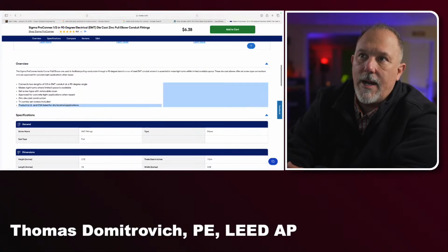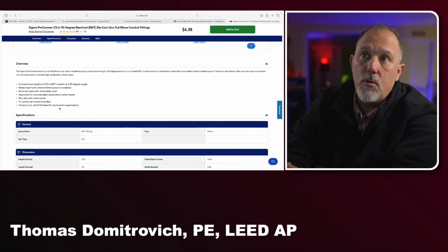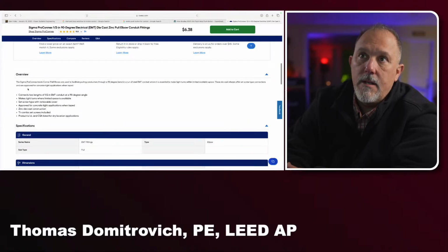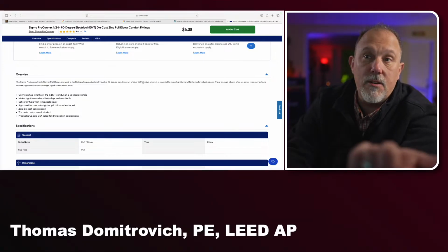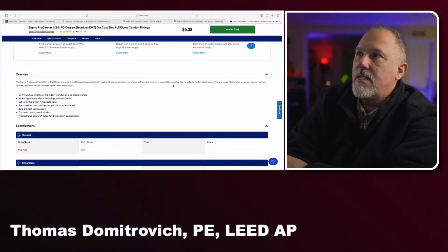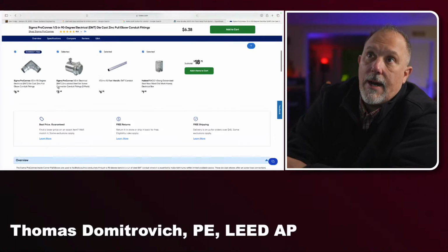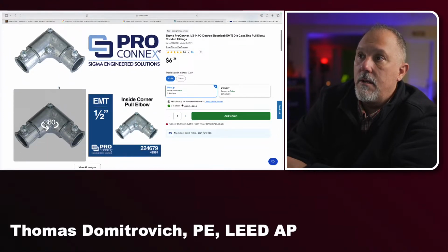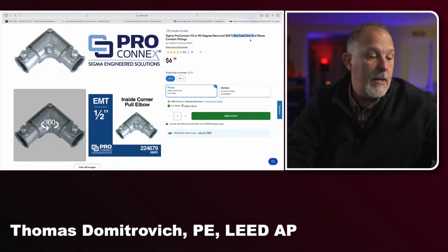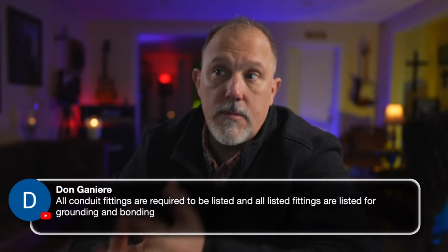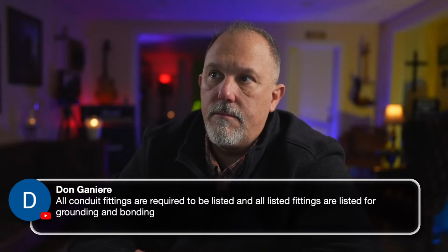Product is UL and CSA listed for dry location applications. So maybe I did not have to pull the equipment grounding conductor. But I did. Sigma ProConnex elbow, 90-degree bend, run EMT conduit where it is essential to make the tight turns, which is what I had. The die cast elbows offer set screw. I don't know why the die cast zinc caused me concern, but to your point, Don, it is listed, so it is probably listed as a raceway.